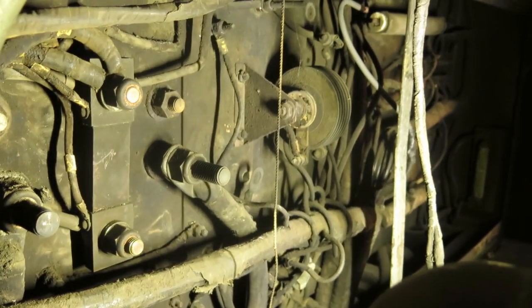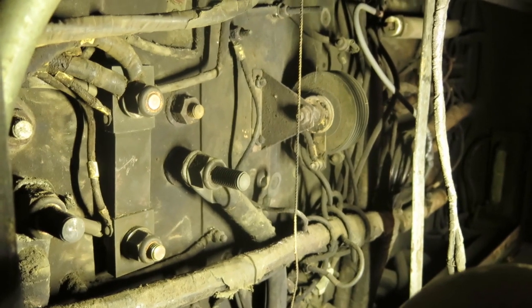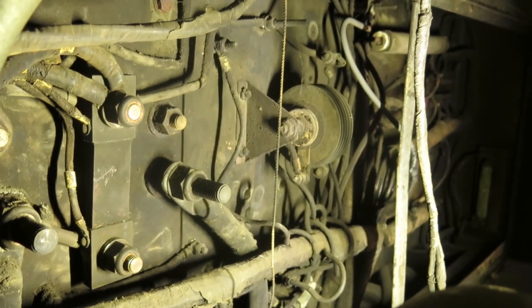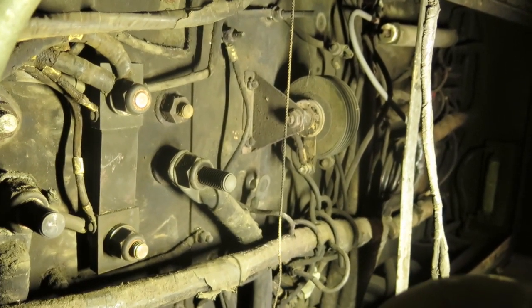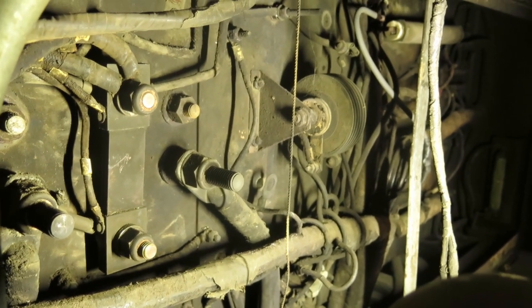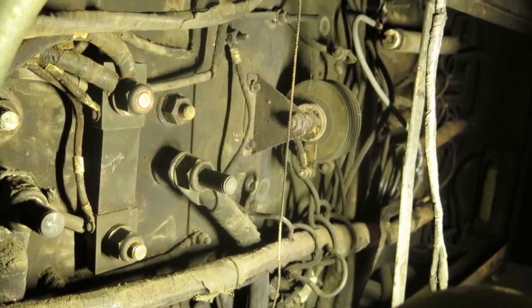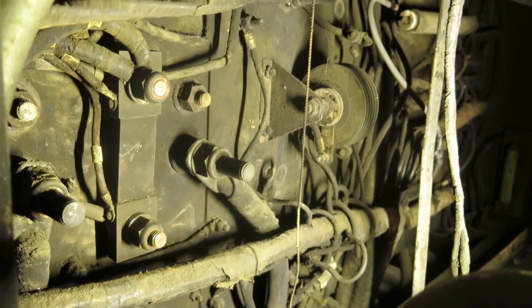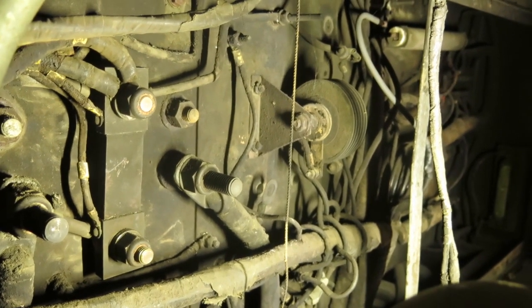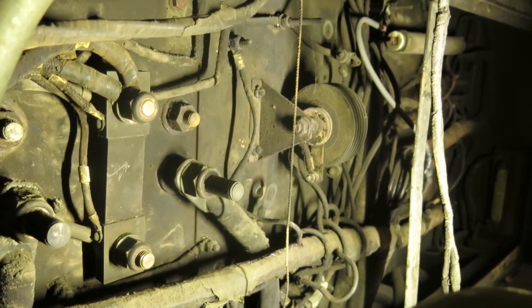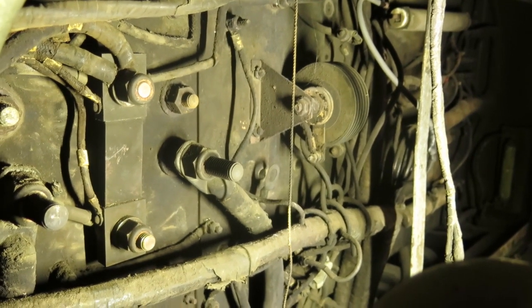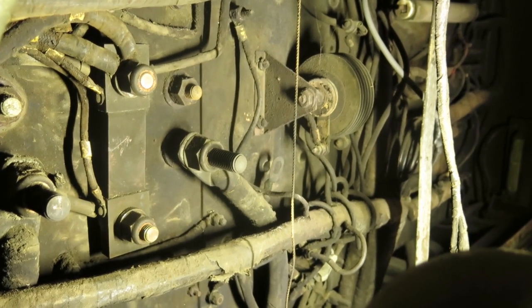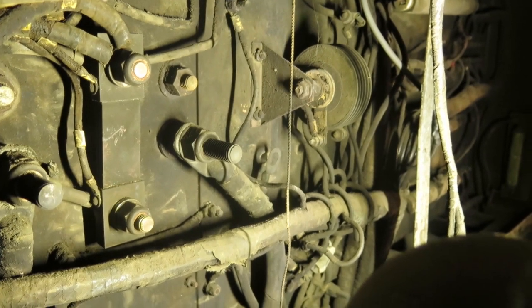So how does one trace out a low voltage ground? Well, after opening all the circuit breakers and switches and pulling the fuses, if the ground hasn't gone away, then it's time to use a meter and check the stuff that's still connected to the battery switch.